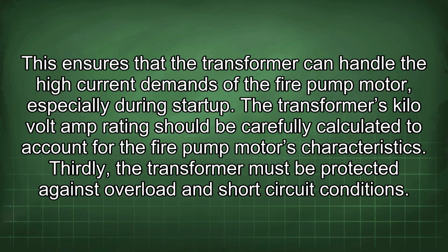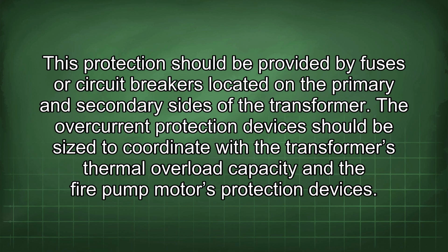Thirdly, the transformer must be protected against overload and short-circuit conditions. This protection should be provided by fuses or circuit breakers located on the primary and secondary sides of the transformer. The overcurrent protection devices should be sized to coordinate with the transformer's thermal overload capacity and the fire pump motor's protection devices.